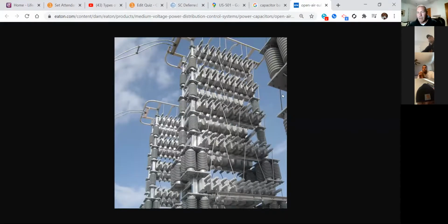Well, what do you think that's doing to the electrical transmission system? Not what we want. Transmission feeds into Georgetown Steel, not distribution. So what do we put at our transmission substations? Take a look at that picture - huge banks of capacitors. Each one of these stacks is for each phase. So one phase of transmission has that much capacitance on it to offset all the inductive load that's on that circuit. Make sense?